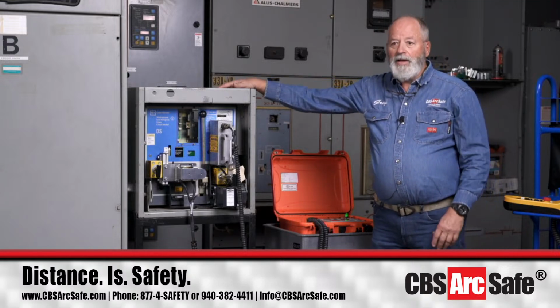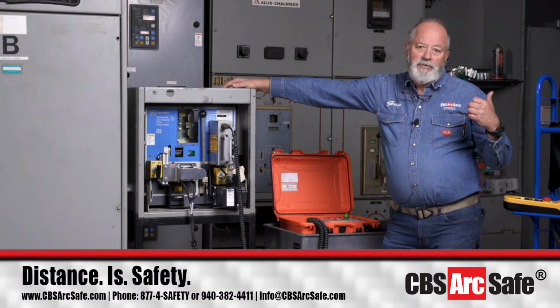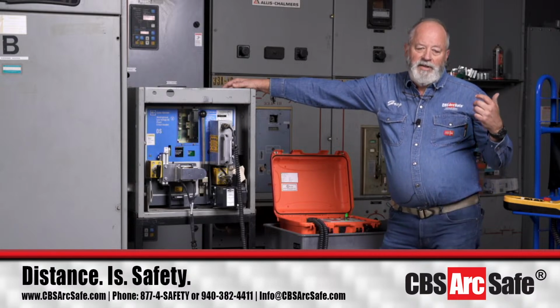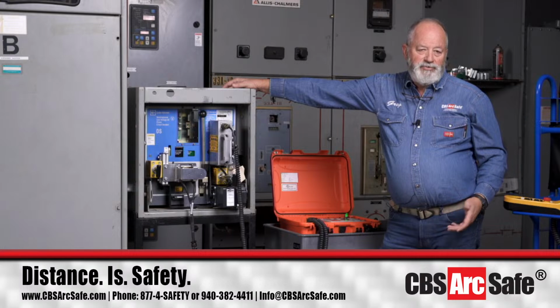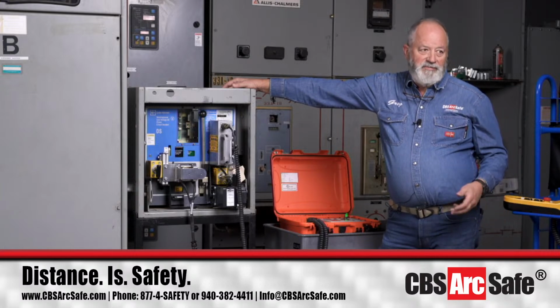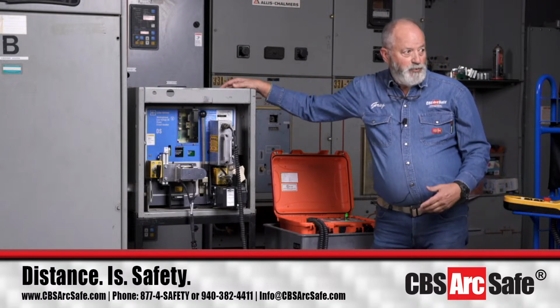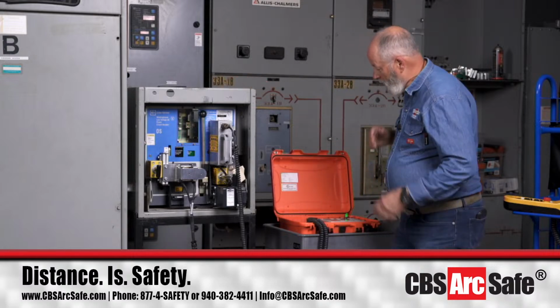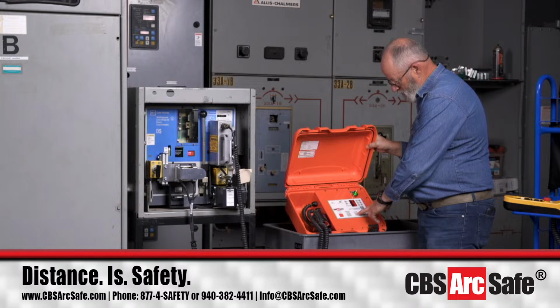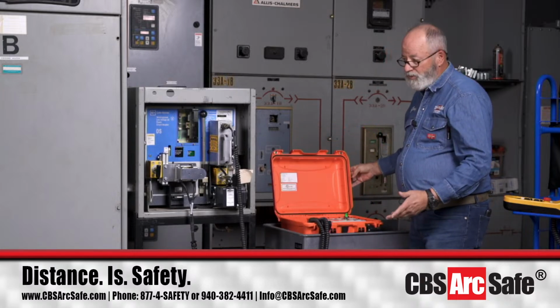So I will tell you, I carried a Magnum DS breaker, and for the year I carried that thing and operated it for 11 months, it was 5 strokes on the handle, and then the last month I was carrying it, it went to 7, it went to 11, and I had to go get the charging mechanism replaced because we'd operated that breaker so many times. Okay, so at this point, we're going to hit the close button and the trip button, and that's the operation of the ArcSafe 12A.